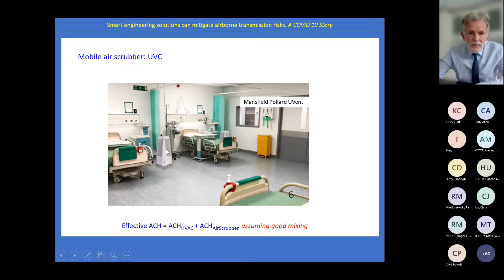This is an example of that kit being put into a 6-bay ward repurposed for critical level care delivery: 6 beds, 4 of these units. The effective air changes per hour are those from the hospital ventilation system, plus those offered by these air scrubbing units.